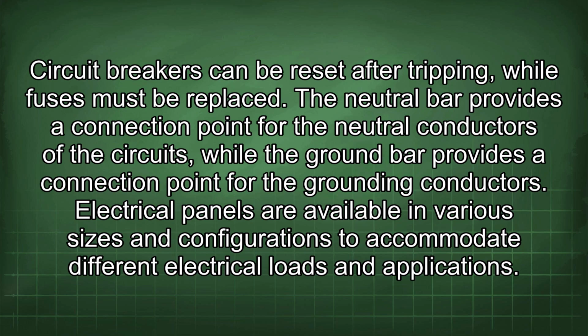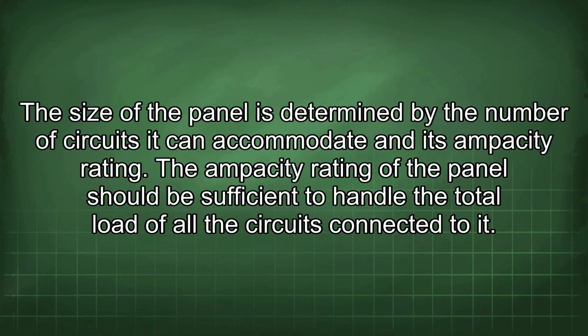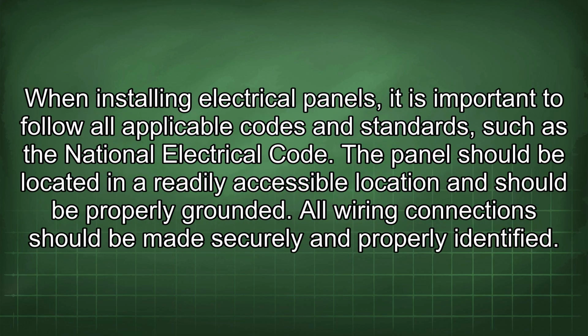Electrical panels are available in various sizes and configurations to accommodate different electrical loads and applications. The size of the panel is determined by the number of circuits it can accommodate and its ampacity rating. The ampacity rating of the panel should be sufficient to handle the total load of all the circuits connected to it. When installing electrical panels, it is important to follow all applicable codes and standards, such as the National Electrical Code. The panel should be located in a readily accessible location and should be properly grounded. All wiring connections should be made securely and properly identified.